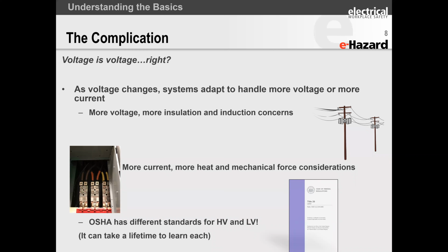So what happens as the current increases and the voltage goes down? Well, folks, as the current increases, you're getting more flow. More flow means more heat. But also with current, you get very high mechanical force considerations. So at higher voltages, where you're getting induction as a concern, at lower voltages, you're getting heating and mechanical forces becoming more of a consideration.